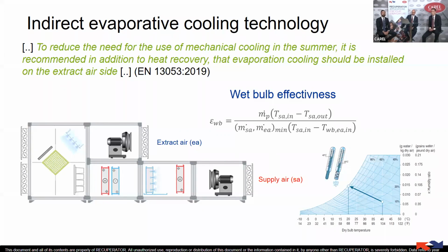We can see what is referred to in the norm 13053, which promotes the use of indirect evaporative cooling together with the cross-plate heat exchanger. But one of the interesting points that we get from the synergy between CAREL humidification and Recuperator is the importance of the integration between the two components. And probably Paolo can give us more advice regarding the increase in cooling effect that we can get from combining an adiabatic, pressurized water humidifier with a cross-plate heat exchanger made in the proper way.